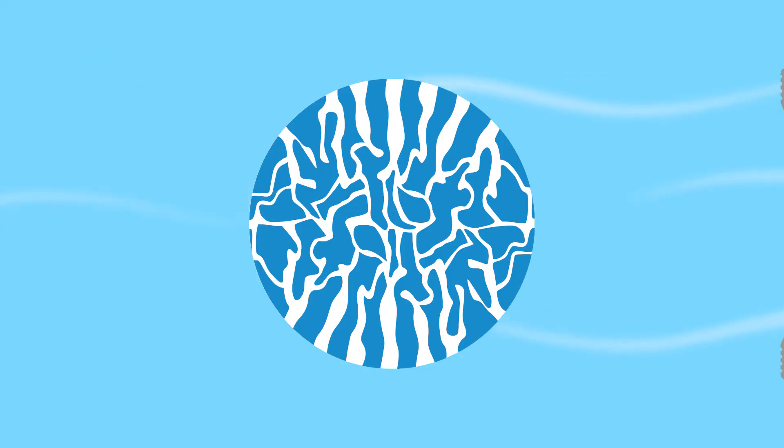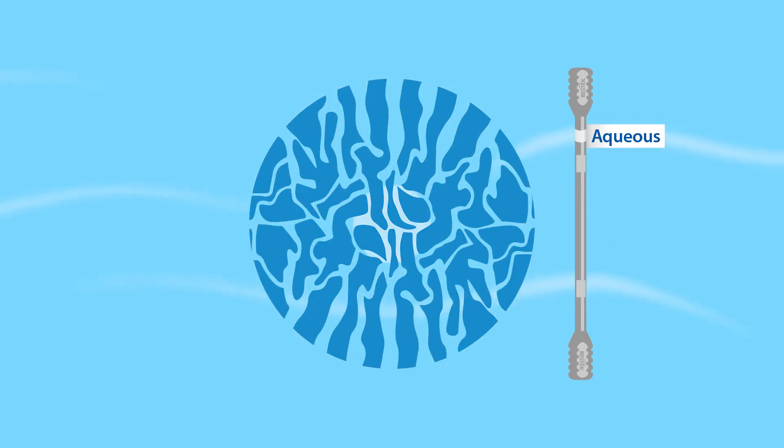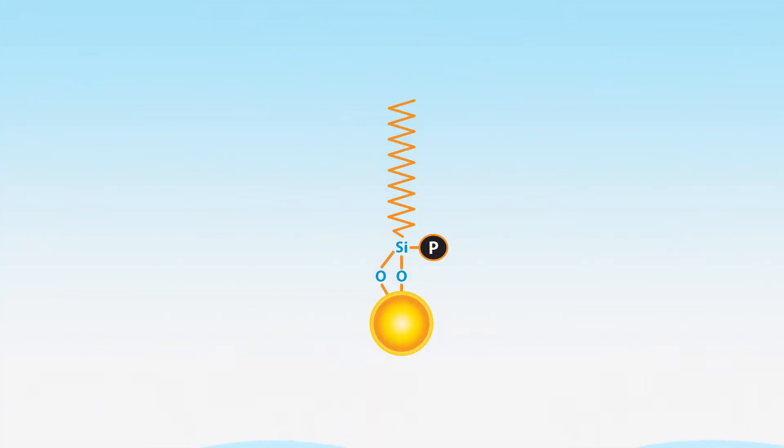So in this case, an aqueous C18 column, which has about 15% carbon load, is recommended. These phases are compatible with 100% aqueous mobile phases, and also provide more retention for polar molecules that need a little bit of an extra boost. This extra retention comes from a polar modification of the phase that also makes it 100% water compatible.